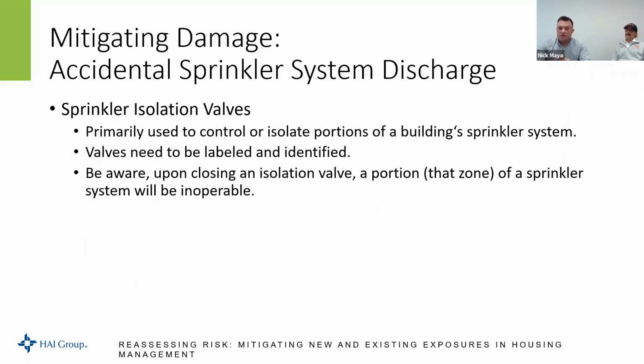So isolation valves in a sprinkler system are primarily used to control or isolate portions of a building sprinkler system. All valves need to be labeled and identified, but as Paul said, upon closing an isolation valve, that zone of a sprinkler system will be inoperable. So let's say it's a 10-story building and the 4th floor isolation valve is closed. Now floors 1 through 3 and 5 through 10 still have water going to that sprinkler system.